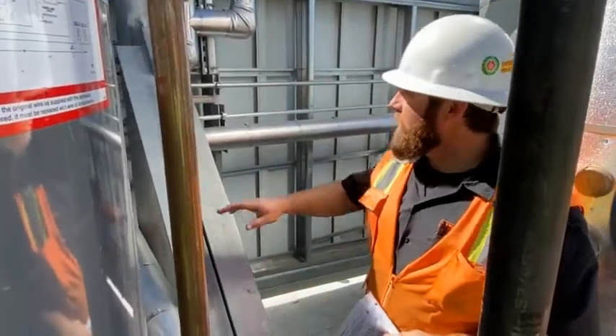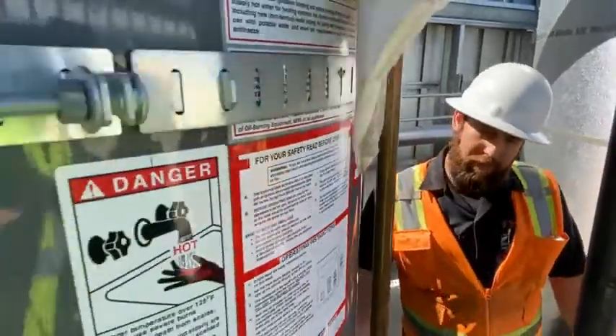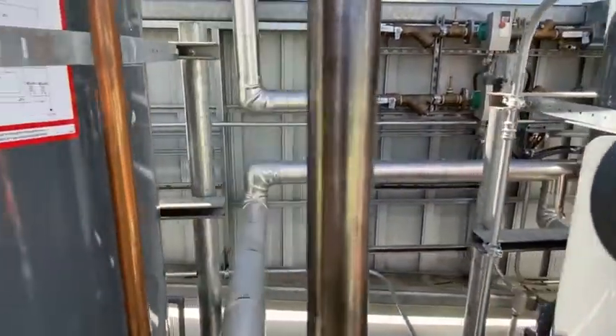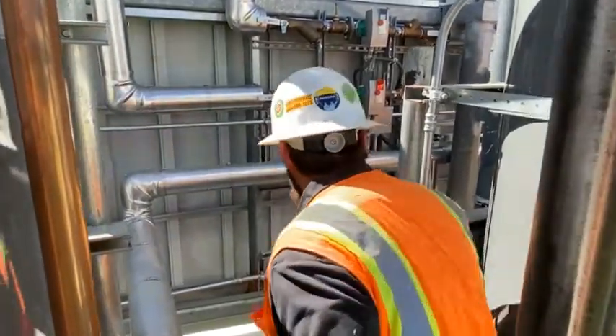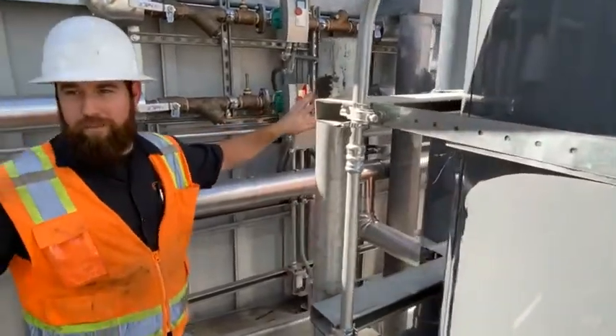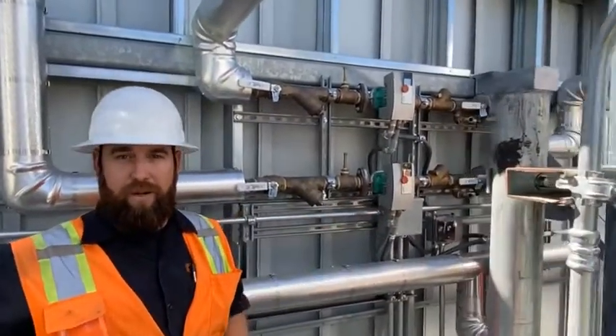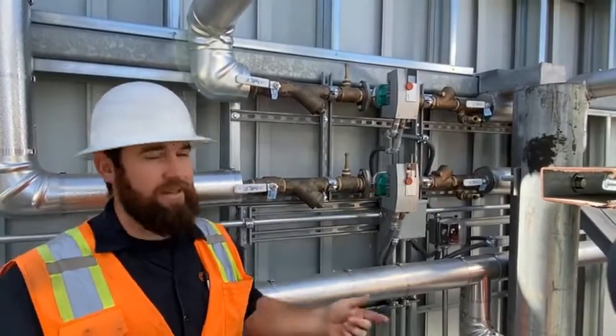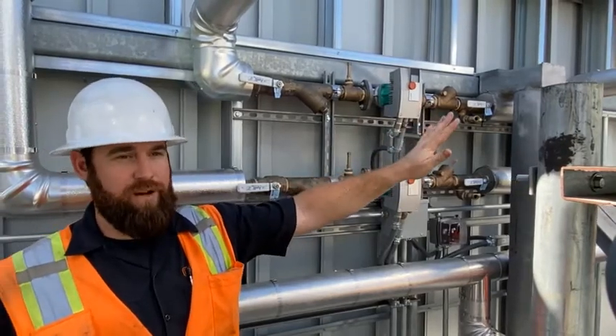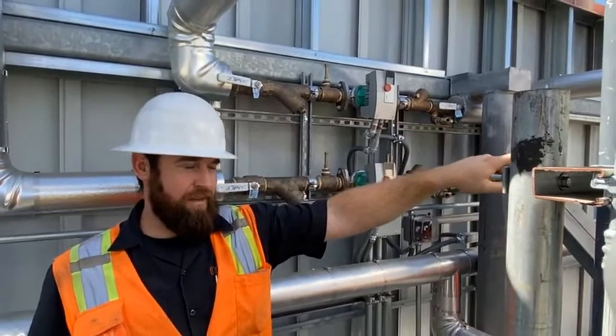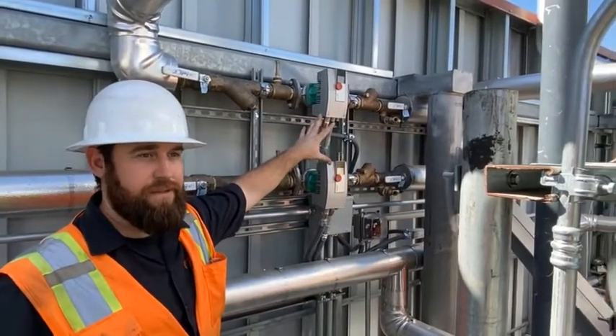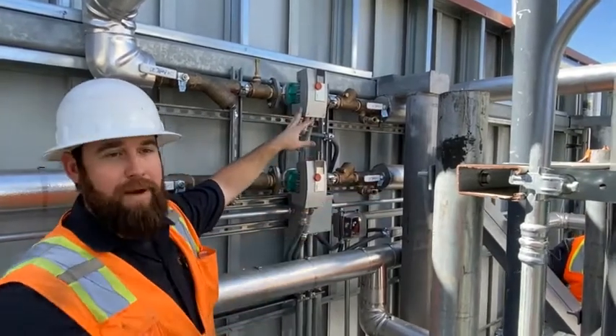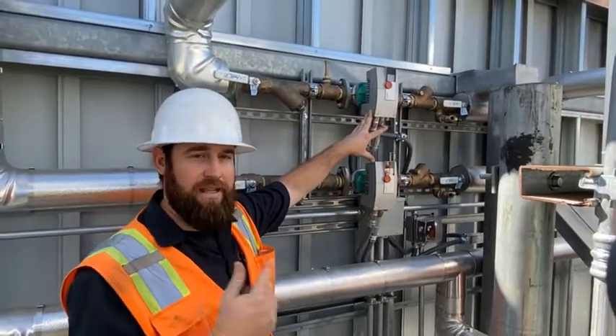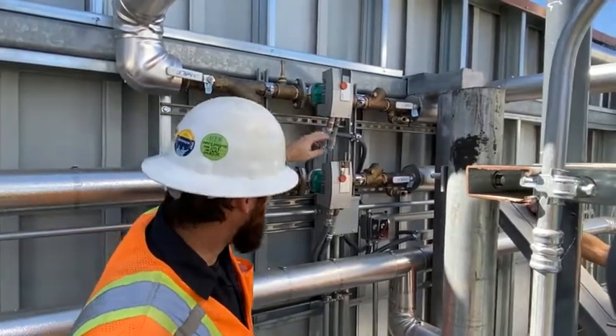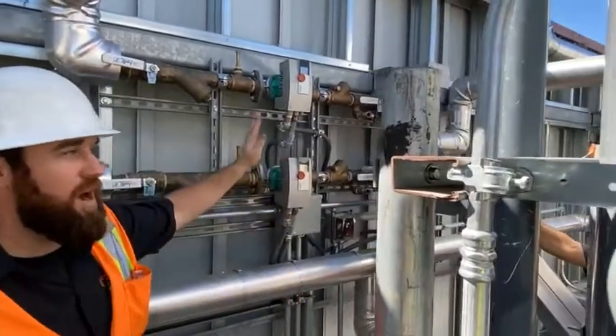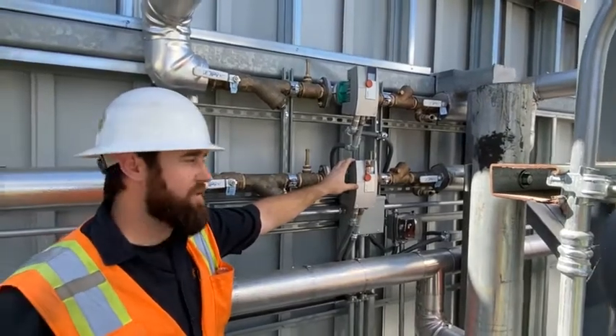All right. So I guess let's get back over here into the pumps. These are Wilo pumps. We're manufacturer rep of those as well. So basically what this is doing is pulling hot water from the water heaters into the storage tank and circulating that way. So we're keeping 140 degrees in the tank. We have two aquastats right there in the box in the front of the tank, which are controlling these pumps. So if we're at 140 or above in the tank, the pumps will shut down. If we're below, we'll turn on, circulate the water to fire up the water heaters. Right now, we have these set. We're at temperature, so they're off, but they run at 3,700 RPMs to circulate water through.